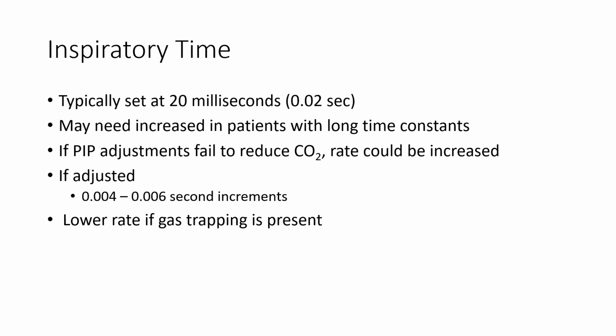However, some patients may benefit from longer inspiratory times. Increasing the inspiratory time can lead to small increases in tidal volume, which could benefit patients with longer inspiratory time constants. If increasing the PIP has been ineffective, up to pressures of greater than 35, for controlling high carbon dioxide and all other settings have been optimized, the inspiratory time could be increased. If the inspiratory time is moved, it should be in increments of 0.004 to 0.006 seconds. The jet rate may need to be lowered to maintain a constant I/E ratio if gas trapping occurs.